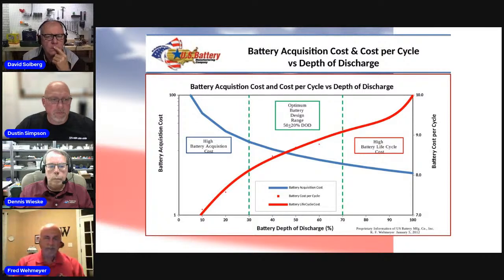This is an interesting slide that I put together some years ago. People often ask, what is the best capacity rating to design my system around? Because obviously it's important not to deep discharge the batteries on every cycle, because you'll pay for it in reduction in cycle life. So what we always tell people is to shoot for about 50%. That does a couple of things. Number one, it manages that depth of discharge, so you get the best optimization of the cost of the installation versus the cost of use, which is measured in the cost of the battery over its cycle life.